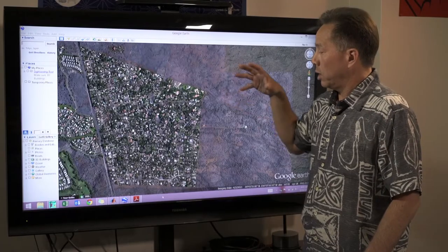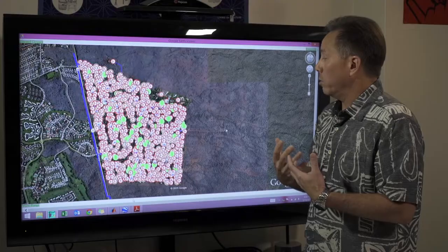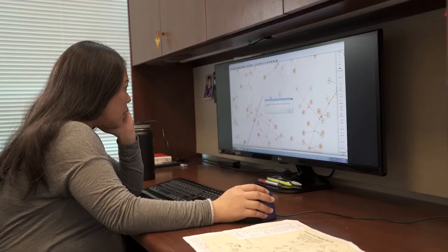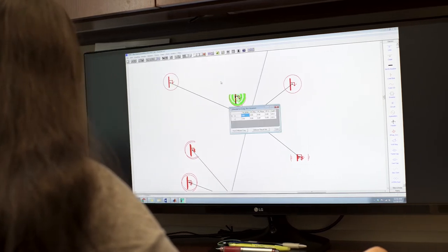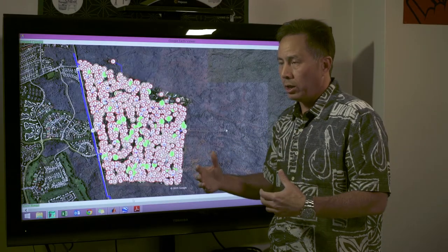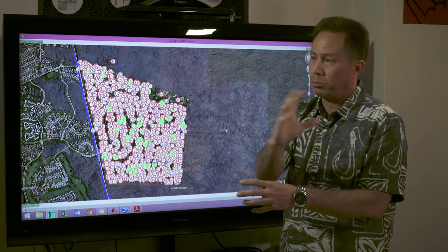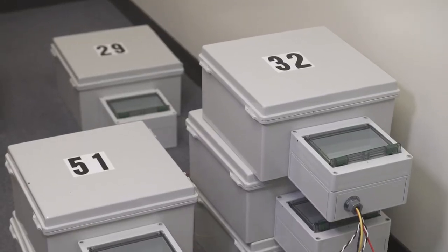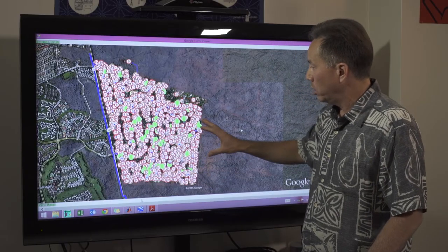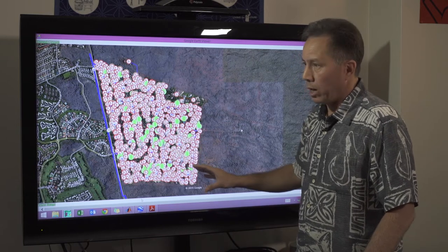This kind of situation is beginning to create issues in managing the power grid with so much renewables. We're trying to address real issues with real-world implementable solutions. We're bringing the technology of smart inverters — enhancing these inverters with advanced capabilities that can read the voltage being experienced on the grid and then operate to compensate for the variability that results from PV power moving up and down as cloud shadows sweep across the neighborhood. We deploy data monitoring devices strategically across the neighborhood to collect not only what the PV panels are doing but also how the power grid is reacting to that.